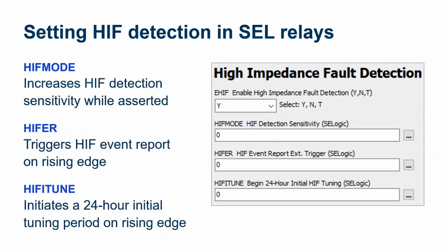We have HIF ER. This is an SELogic equation that allows us to trigger a high impedance fault event report. It works similarly to the ER equation that's in many SEL relays that you may be familiar with, except this is going to trigger a high impedance fault event report, which is different than our traditional event reports. Hardesh is going to go into more detail in a later section. These are not going to include the full oscillography. They're going to be over a span of minutes rather than seconds or cycles.